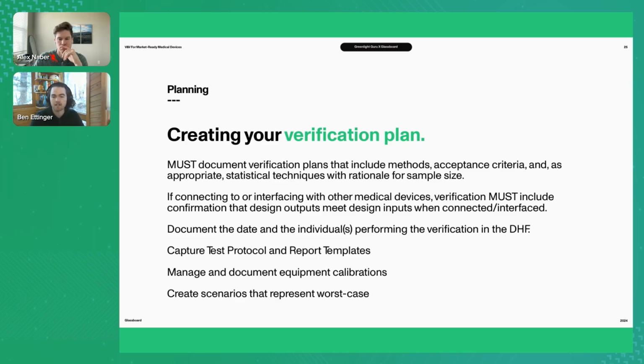And then on the documentation front, just always every step of the way, looking at who is doing what when they're doing it, having that paper trail to stand by. This is a great stage to push out test protocol and report templates for your team to execute on and start on an equipment calibration strategy. So you're likely going to have a suite of testing that's going to be in-house and a suite of testing that is going to be out of house. And just making sure you have a strategy for what equipment you need in place, what calibrations you need, and making sure you have the documentation in place to prove out those calibrations.